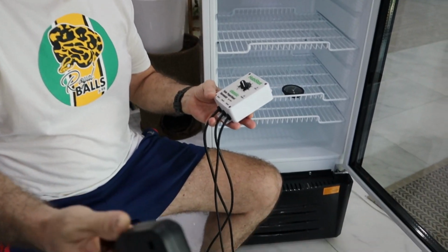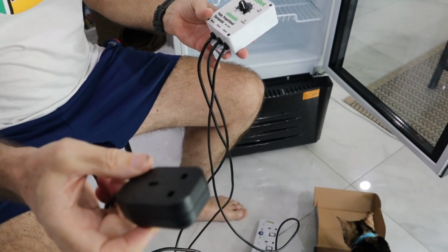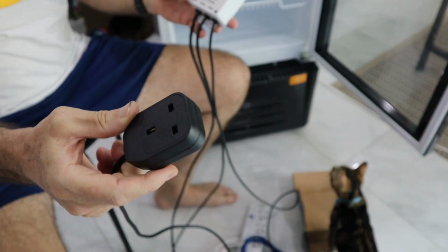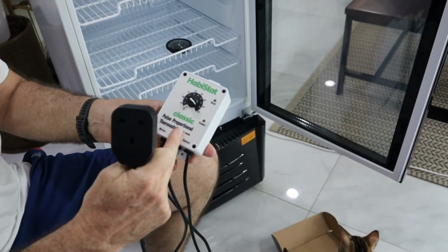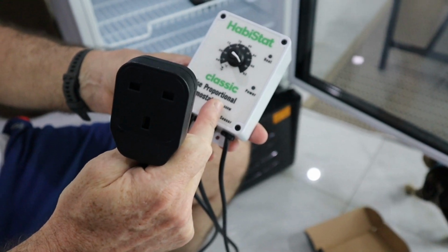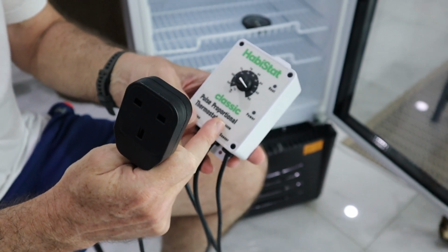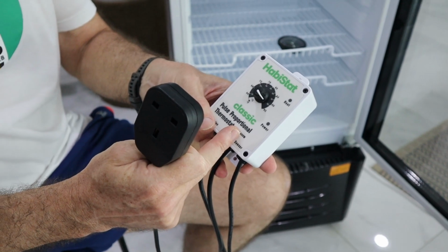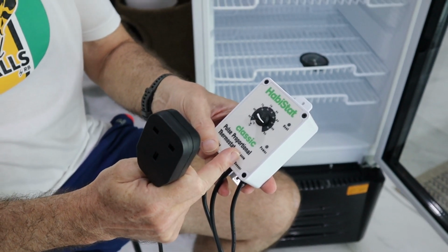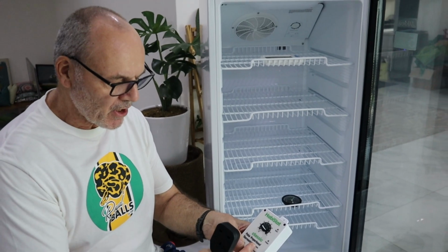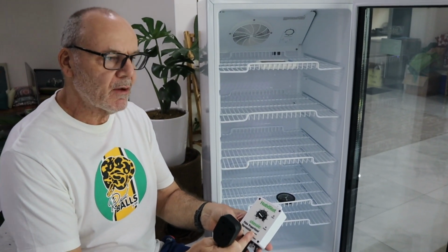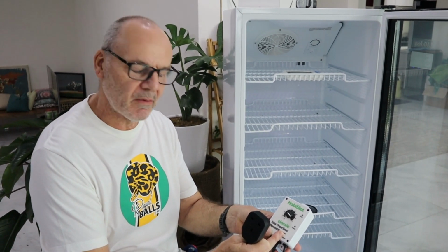This is the power outlet for the heat cable to go into, and because this is a pulse proportional thermostat, all thermostats are actually fairly simple. They switch the current on and they switch the current off. An on-off thermostat will have a desired temperature, and it will switch on if the temperature drops a certain amount below that temperature, and switch off when it rises a certain amount above, usually about a 1 degree C window.